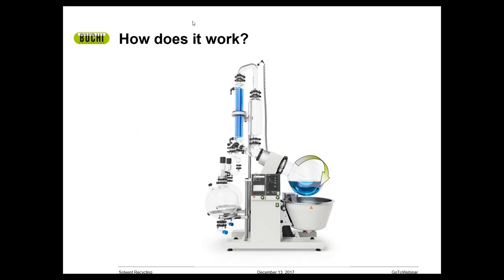So how does it work? There are a couple of key parameters. First is the vacuum. The next important parameter is rotation — using a rotary evaporator, rotation gives you a nice, even surface area around the glass, increasing the surface area of evaporation for your sample. With just atmospheric method, the only surface area would be at the surface of the liquid. But with rotation, you have a thin film coating the glass, so you get not only the surface area of the liquid but all the way around the flask too. This increases the rates of distillation and makes the process much faster.